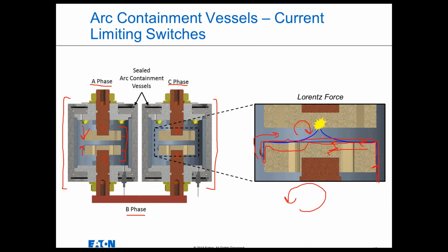What that does is cause the top half of that wire to be repelled from the bottom half, and it jumps up and out of the way. But lo and behold, it can only jump so far and hits that top contact. There it momentarily ties phase A to B and phase C to B. But that wire is so thin that it can't conduct full available fault current and voltage. So that copper wire melts, it vaporizes, and then it ionizes. And when you ionize copper, you have an arcing fault. So we've spontaneously created two fully contained arcing faults that tie all three phases together inside the arc containment vessels.